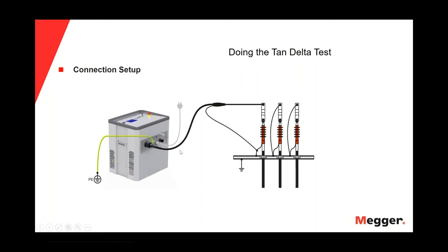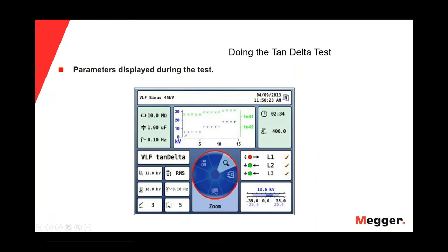And if we see the display of the unit, we will see the most important parameters during the test. We are seeing in this case the step voltages, the three step voltages, and the tan delta associated for each voltage step. Okay, we can see also the resistance, the measure of the resistance of the insulation. We can see the capacitance of the cable, of course, the frequency, et cetera, okay?